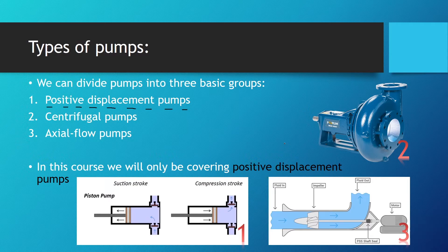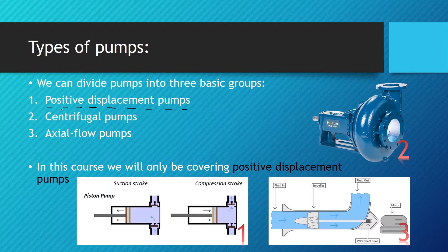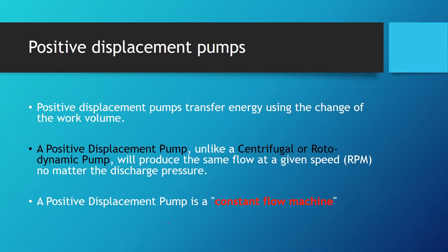A positive displacement pump transfers energy using the change of the work volume. As you can see here, the piston pump changes the work volume — it reciprocates left and right and that way it pumps fluid. A positive displacement pump, unlike a centrifugal or rotodynamic pump, will produce the same flow at a given speed regardless of discharge pressure.